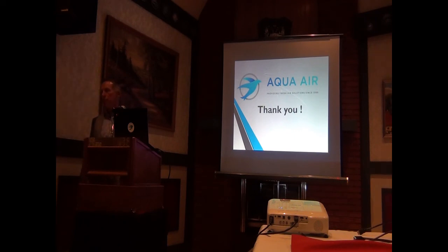But anyway, from a retrofit perspective, or optimizing the existing equipment without having to sell the farm, it's not that expensive to do some retrofit. You get what you pay for in life. You pay now or you pay later. That's the secret. Nothing changes. But you are right with the variable, everything should be variable. It's amazing how much energy you can save. Control the refrigerant process. You can optimize the process to try to get the most you can out of what you got. Everything has a VFD today. I call them just a smart dimmer switch, but it just makes it easier to control your inrush. And you control with a pump. A pump is very efficient because you got full flow all the time. On an HVAC, it's not as efficient because you got almost 2.5 inches of variable in your filters as they're loading up.